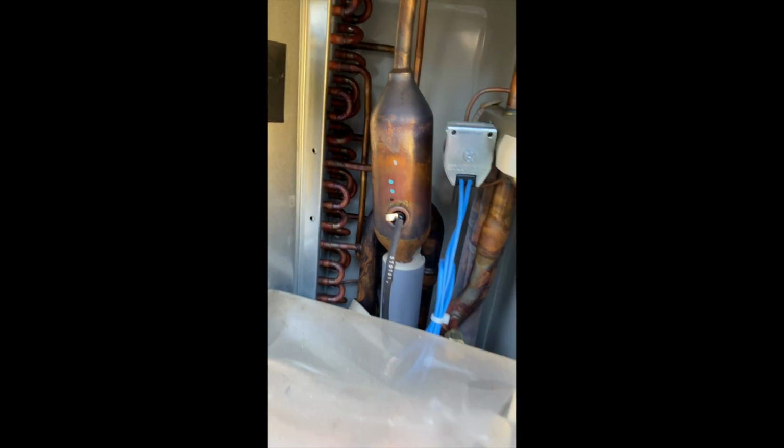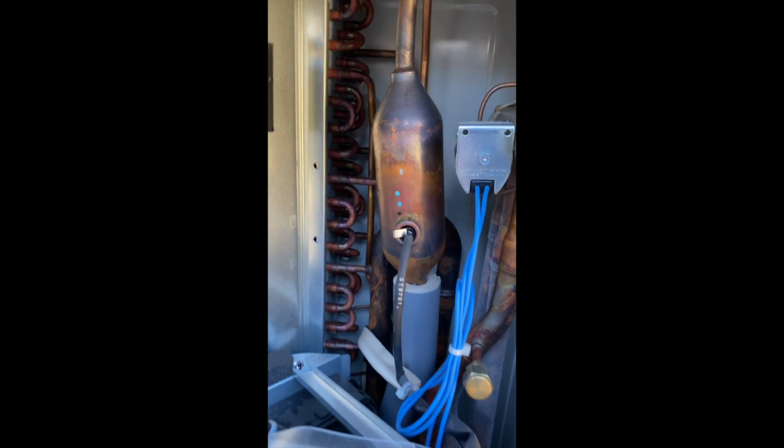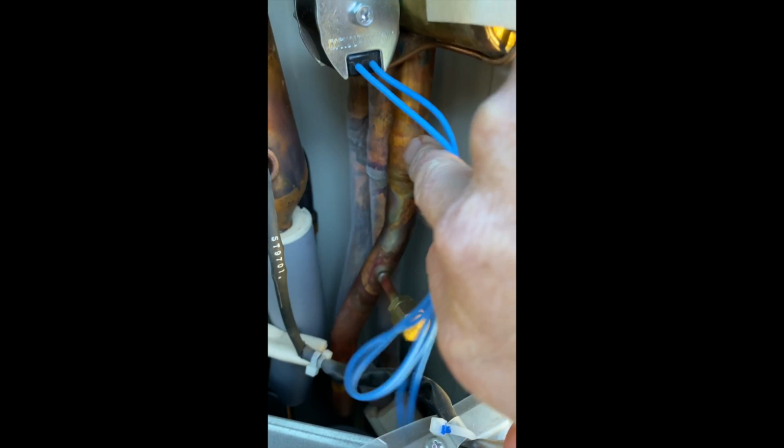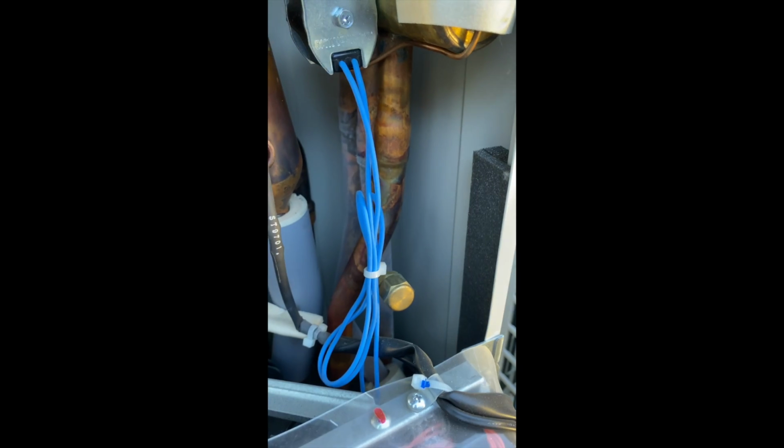Okay, flipped over to recording with my phone because my trusty old camera card's full. Anyway, so the unit's still in defrost. We'll flip it over again. The coil is just about all melted. So you can see there it's completely free of ice. Water stopped dripping out of it. So in a second we'll get the reversing valve changing over. That's the reversing valve here. You can see these two pipes at the back. There it goes, just changed over.